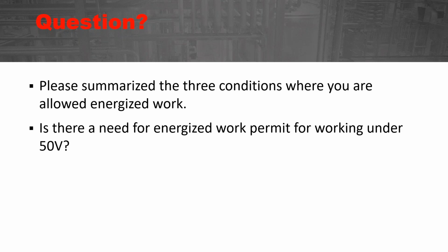The question is, is there a need for an energized work permit for working under 50 volts? Let me give you this. 130.2A3 says equipment operating at less than 50 volts, that's the title. Energized electrical conductors and circuit parts that operate at less than 50 volts shall not be required to be de-energized, meaning it's not required to de-energize. It goes on. We can't just stop there. It goes on to say where the capacity of the source and any other overcurrent protection between the energy source and the worker are considered, and it is determined that there will be no increased exposure to electrical burns or to explosion due to electrical arc. So you can't just say anything and everything less than 50 volts. We have to look at the other parameters of that section. Is there anything else that could increase the hazard and make it dangerous?